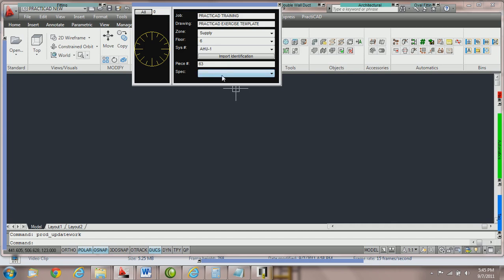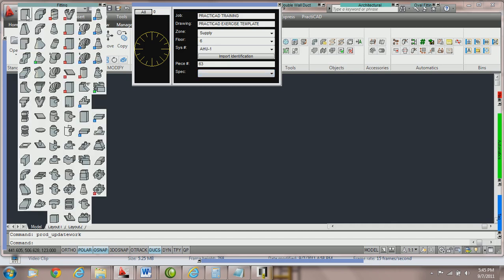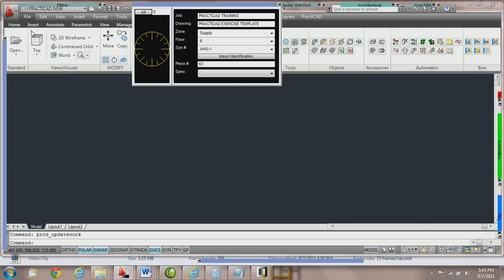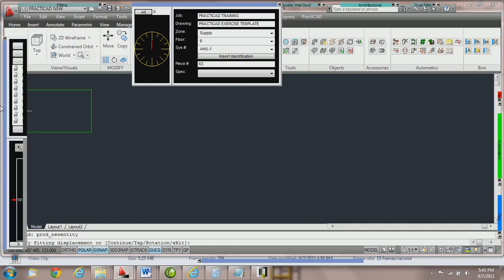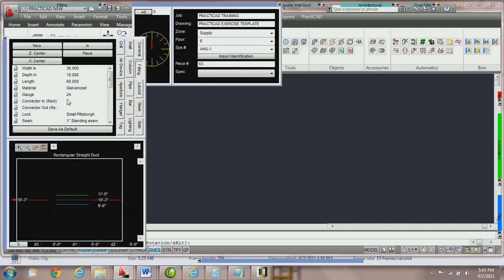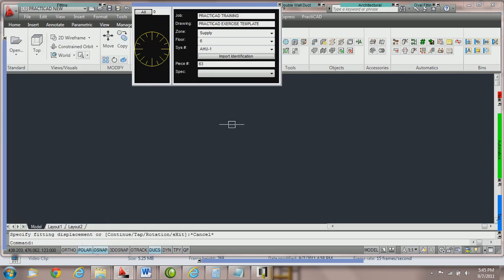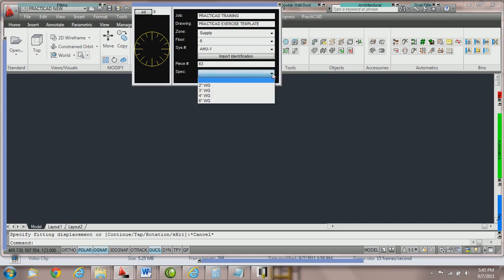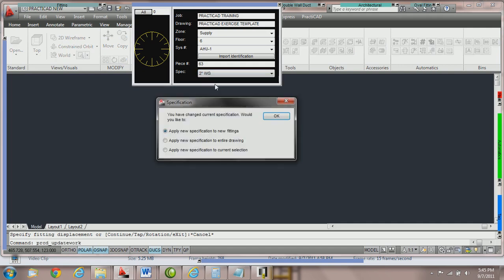Notice currently that spec has nothing selected. So we're going to grab a fitting and go into the fitting parameter box and you can see that it has no connections. This is a great indicator that there are no specifications in play. However, if we come over to the workbox and pull from our drop down menu and say, let's use two inch water gauge, the choices will vary depending upon what your specifications are.